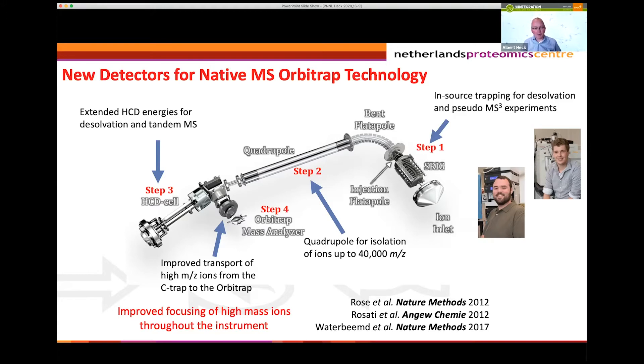We worked together with Thermo Fisher and developed a new generation of orbitrap mass spectrometers. The first one was called the EMR, the orbitrap with extended mass range. And in 2017 we co-developed the UHMR, which stands for ultra high mass range orbitrap mass spectrometer. The instrument doesn't look that different from a standard orbitrap, except that there are several modifications in RF fields to get better transmission of these slow, high-mass ions. A special quadrupole is also included that can select high mass ions at high m/z for further experiments downstream.